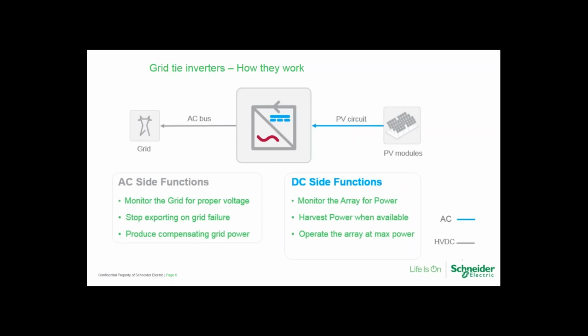So before talking about AC coupling, we should explain just how a grid tie inverter operates. A grid tie inverter is typically a current source only. They cannot produce a usable waveform, hence they cannot be used for backup. This means if the grid goes down, solar production ceases. These applications typically have net metering, and excess solar is exported to the grid.